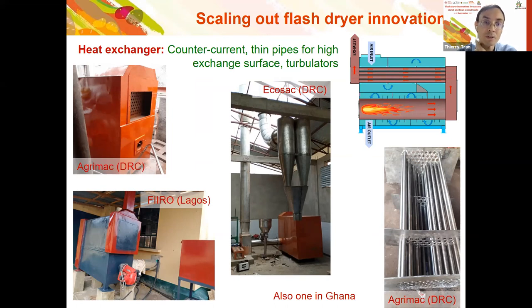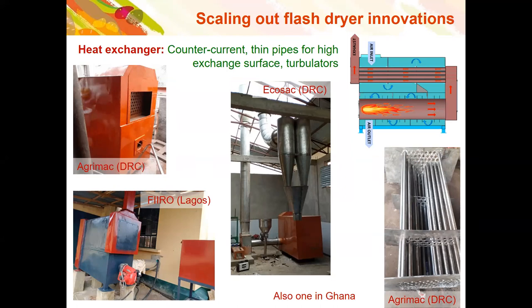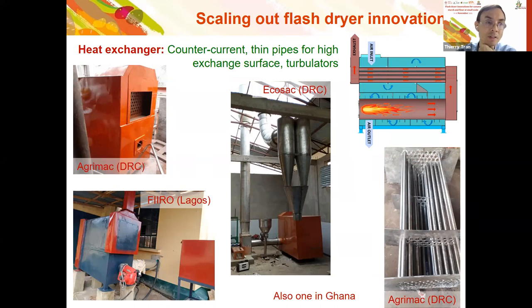And then to have a series of chicanes and thin pipes to have the maximum possible exchange of heat from the fumes from the burner into the fresh air. We also used retarders to increase the turbulence of the fumes, to slow down the fumes so there is more time to transfer heat to the fresh air. Those improvements have resulted in energy savings between 30 and 50%, so cutting the consumption of fuel by between 30 and 50%. Here are examples of the new model of the heat exchanger being installed in different factories in Congo and in Nigeria.